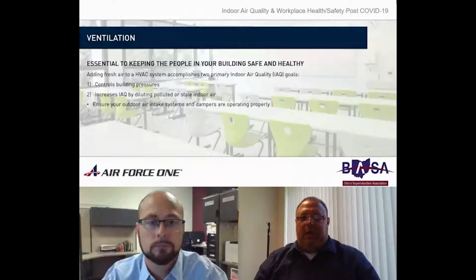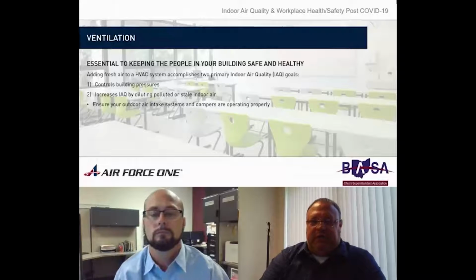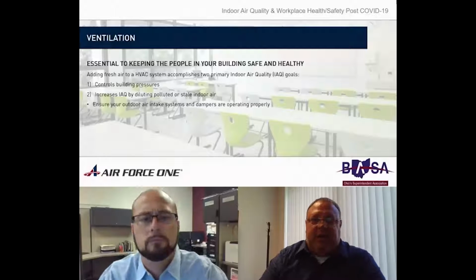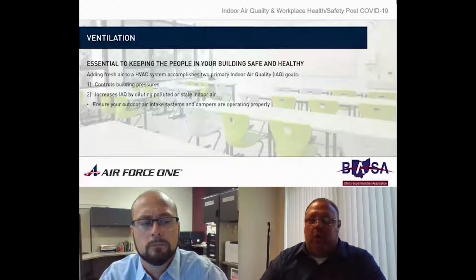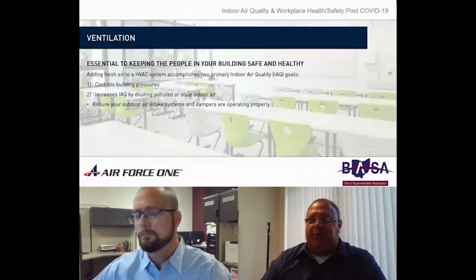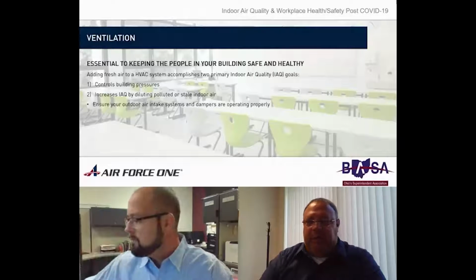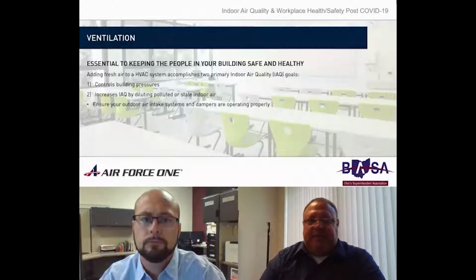Yeah, and specifically for schools, as Austin said, ventilation is key to having a healthy building. With that said, one of the first items that is removed, minimized, or completely disabled is your outdoor air economizers. I know many of you on here have gone through House Bill projects, which are energy based. The biggest thing to do is reduce outside air to help maintain your cost per square foot, and to maybe get a handle on some insulation that wasn't good. The other thing that happens is when you start having problems with equipment and the outdoor air damper possibly has failed, or you're having trouble heating or cooling, a lot of companies will go in, disable it, minimize it, or not allow it to open as far as it can, which of course decreases outside air and causes building pressure problems.